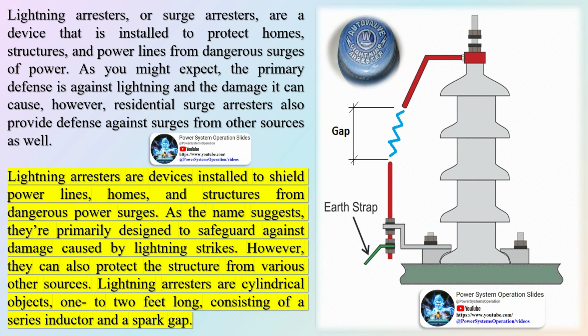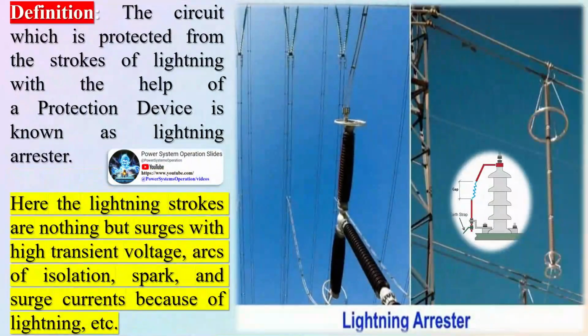The circuit which is protected from the strokes of lightning with the help of a protection device is known as a lightning arrestor. Here the lightning strokes are nothing but surges with high transient voltage, arcs of isolation, spark, and surge currents because of lightning, etc.